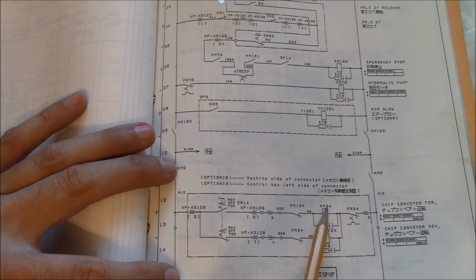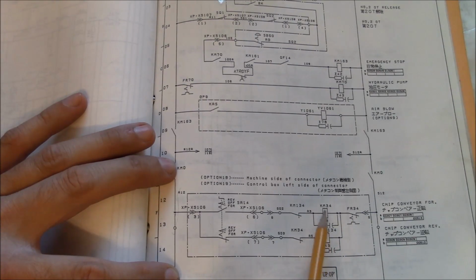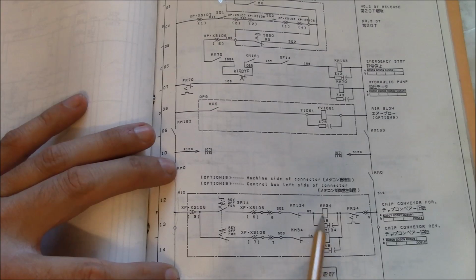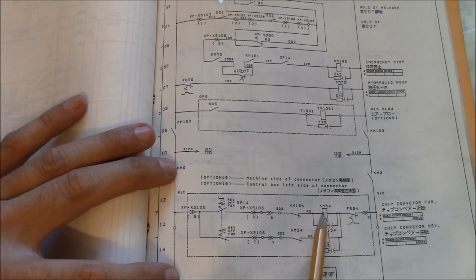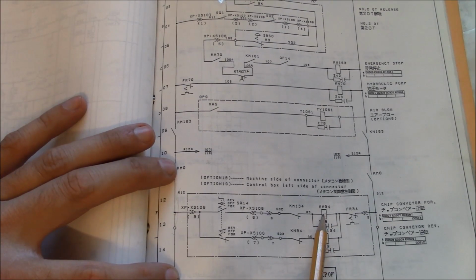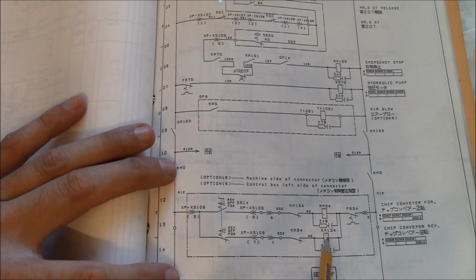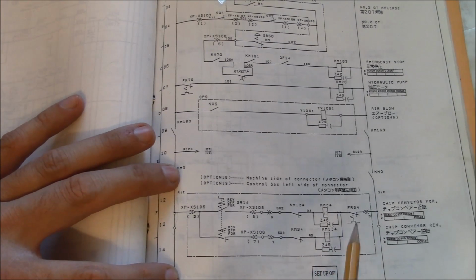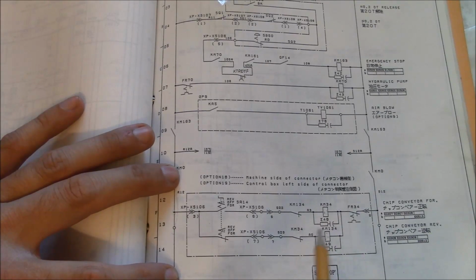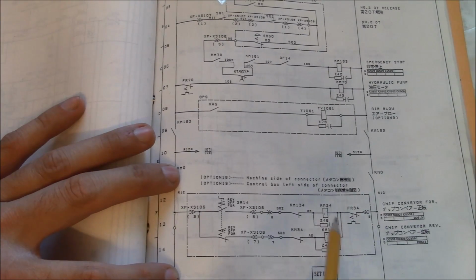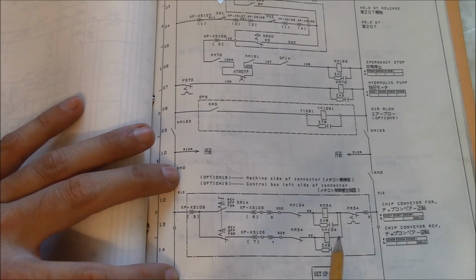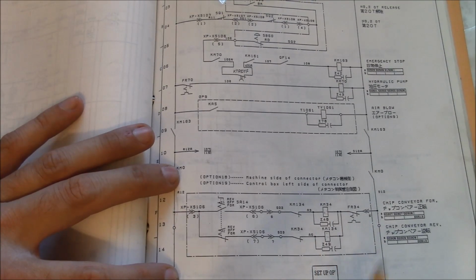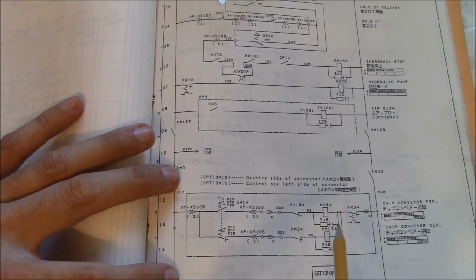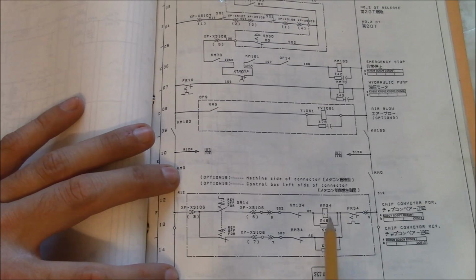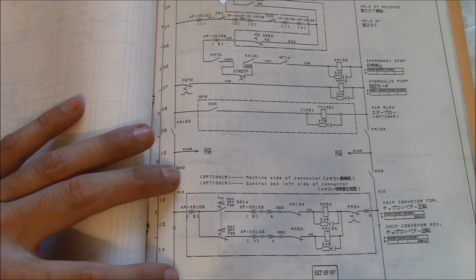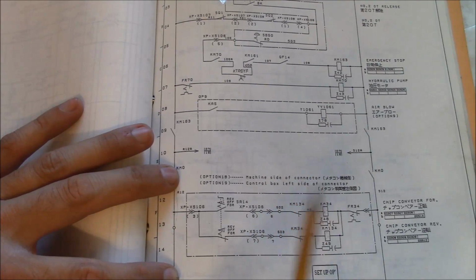KM34 and KM134, these rectangular boxes, that's the coil for a relay. So if I go to the machine, I can find KM34 and KM134 as physical relays, and that's what controls my conveyor. This machine is fairly old and doesn't have a PLC that can handle this kind of amperage. Today it's very common to find a PLC that can switch 5 amps, but in this machine they actually use relays.